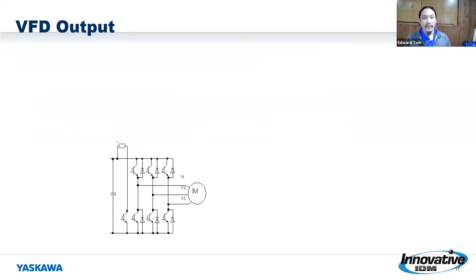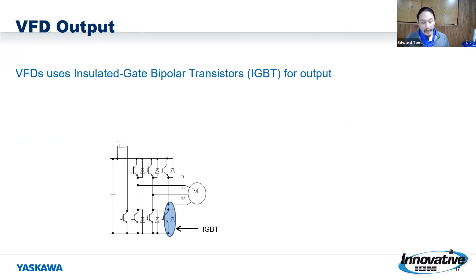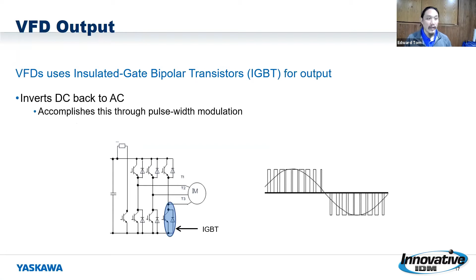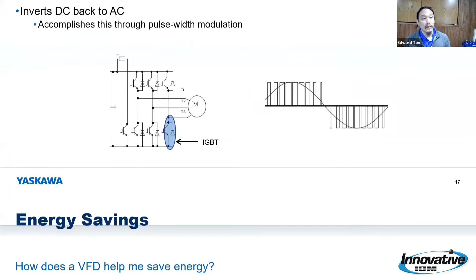So there's only flow through there when there's actually higher voltage on the input side. So now that we've got the DC bus charged up, we now need to take it and turn it into that regulated pulse voltage, the pulses that we were talking about. So now we're taking the DC, and with the IGBTs, the insulated gate bipolar transistors, we're pulsing that and sending it out to the motor, and then regulating it so that it gives us that voltage and frequency that we were looking for, that I was mentioning. And now we've got that control. So the basic topology is there, but how does it really help me?